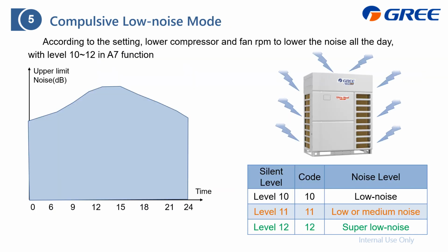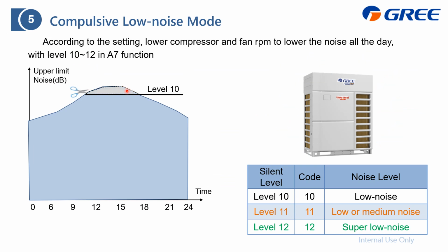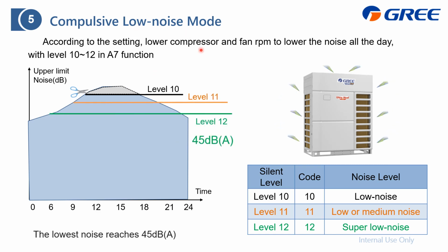If you find the outdoor unit is still noisy, you can choose level 10 to level 12 to force lower the compressor output, and this is also called compulsory low noise mode. With this one, we can lower the compressor output to lower the noise to be as low as 45 decibel A. And I'd like to emphasize that this is the outdoor unit noise, not the indoor unit.